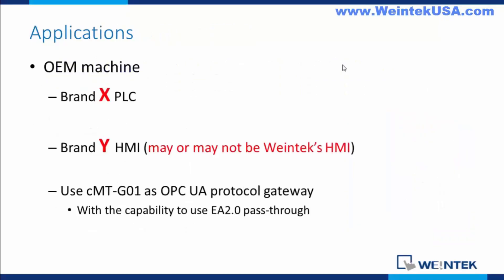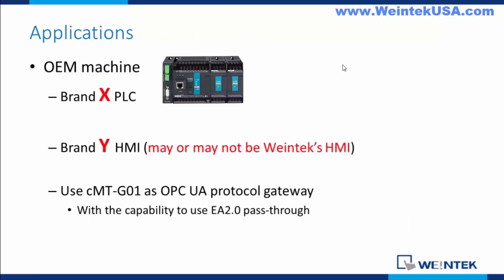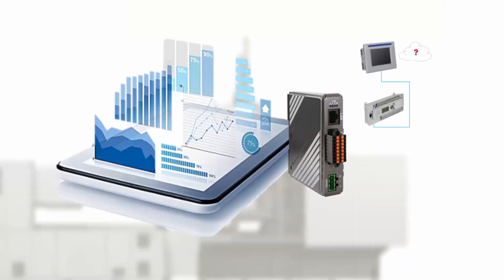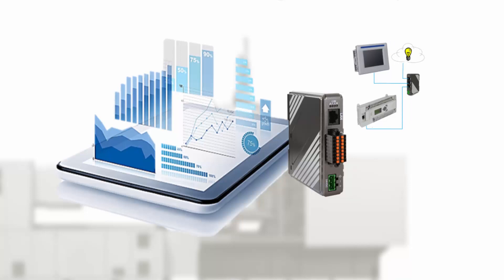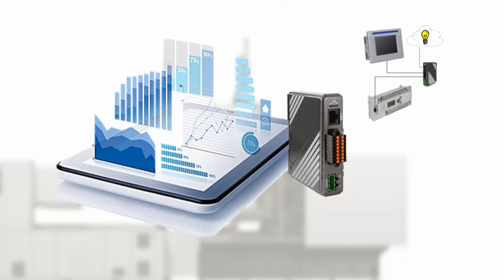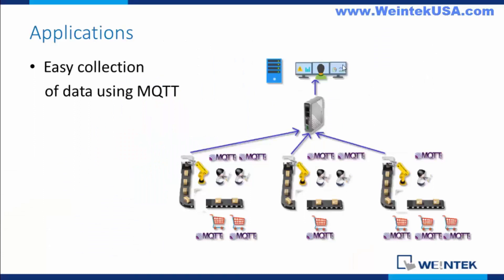A couple of scenarios where these may come in handy. Let's say you need to establish communications between a brand X PLC and a brand Y HMI — it may or may not be a Weintek solution. You can use the cMT-G01 as an OPC UA protocol gateway. You have your Easy Access 2.0 pass-through capability to communicate with those non-Weintek devices and their native software.